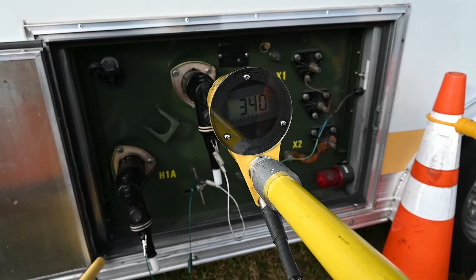So what we're going to do first is take a phase to ground reading. The reason is that we're going to verify the tool's working, verify that our head's in the game, and take that number and remember it. Because each elbow is going to be different, we're going to see the difference of the two values when we go phase to phase. We won't see zero, we'll see the difference of the two.